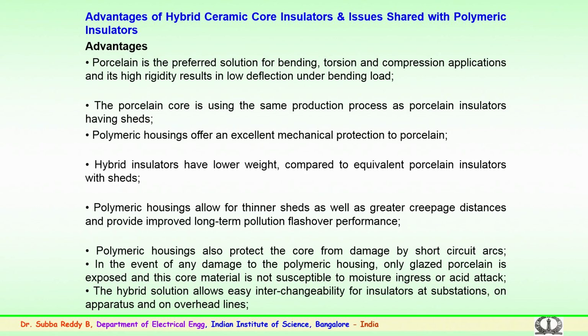Polymer housings allow for thinner sheds as well as greater creepage distances, and provide improved long-term pollution or contamination flashover performance. This is one reason why even transmission line insulators, such as ceramic or glass insulators, are being replaced by utilities in areas where contamination or pollution flashover is a serious issue. So polymer housings perform better with thinner sheds compared to porcelain insulators.